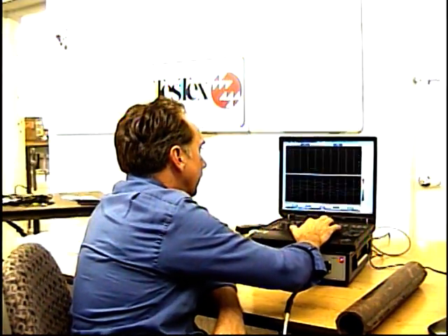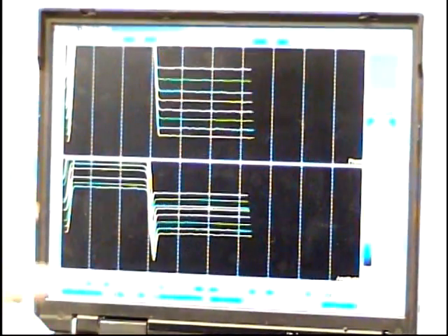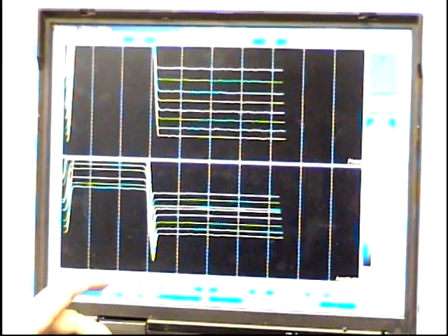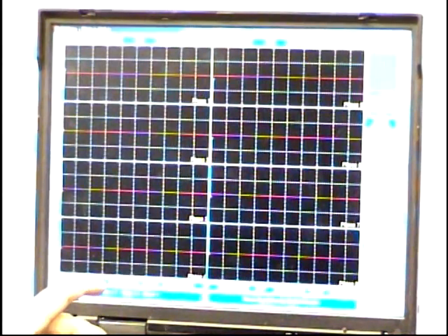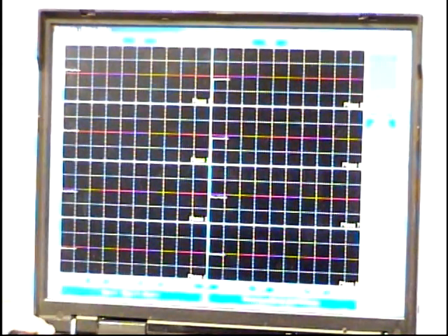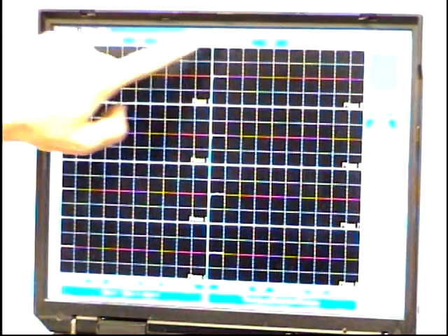Now, I'm going to flip this tube around to show you what it would be like if there was a clean tube with the same type of material and same wall thickness. You're going to notice my signal is straight. Let me get back to the original screen that I had. You'll notice the 4 or the 8 channels again.